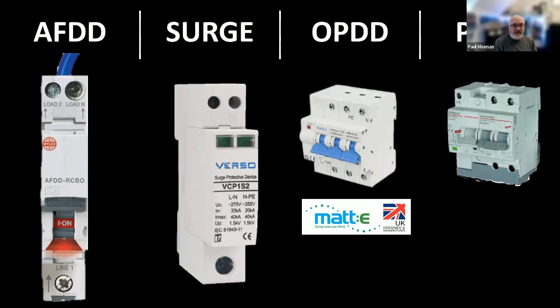And if you look around the world, you've also got something called a POP device. Now, a POP device, similar to a surge, but rather than looking for thousands of volts, it will look for voltages outside the normal bands. Say you get 290 volts single phase to earth. It will look at that for a few seconds and then disconnect to protect your installation from any stresses or strains because of the network.